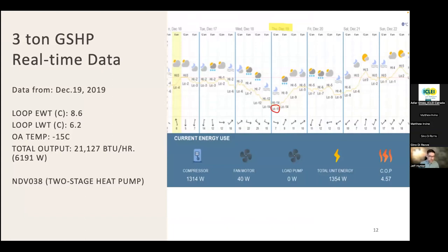To compare that then to geothermal. Now, this is field test data, and this is a shot from actually a WaterFurnace brand piece of equipment. They have a very nice interface called the Symphony system. And so the homeowner can see exactly what kind of energy that they're using. And here, this is real-time data, from 2019 because I had it in a slide. This was Hamilton, Ontario, outdoor air temperature minus 15 Celsius, what we can expect. We can see the system is performing with a COP of about 4.5. So this is a really well-performing system in this situation.